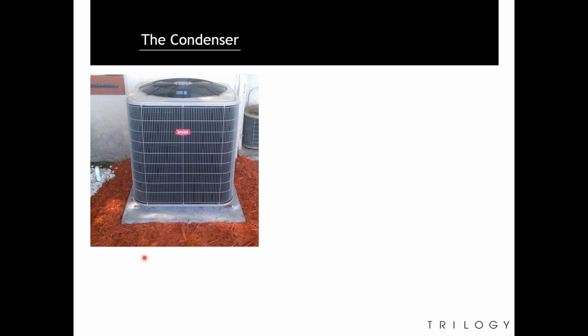So if you have the luxury to start at the condenser, start there. It gives us clues if the problem is inside or if it's at the unit itself, just by walking up to it. So what do I check for? We want to check to see if the condenser is running.